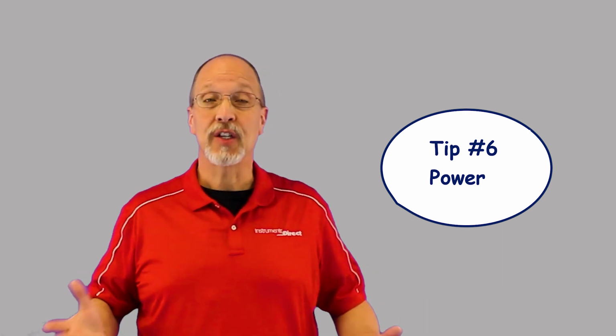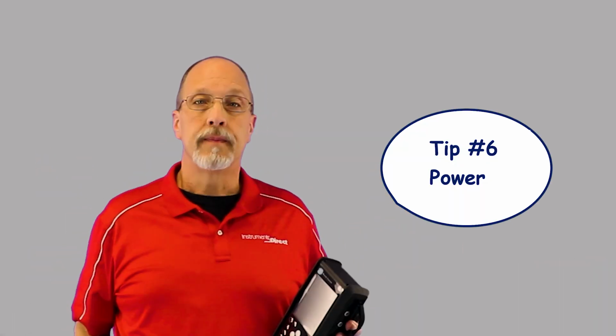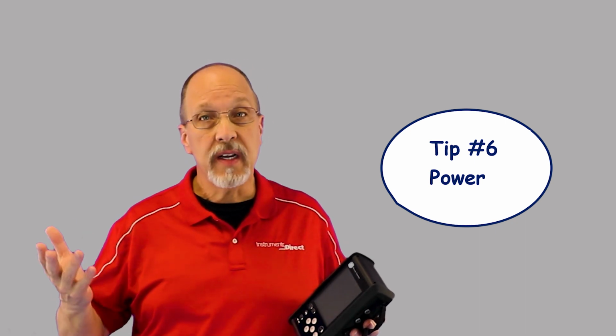Tip number 6, power up. If you're just making a spot check, well, you can probably get by just hand holding the transducer on the pipe and get by with the flow meter battery. Now, the Fuji will last for about 12 hours. If you're conducting a longer flow survey for a day or longer, you'll need to plug into a wall socket for power and trickle charge the meter.